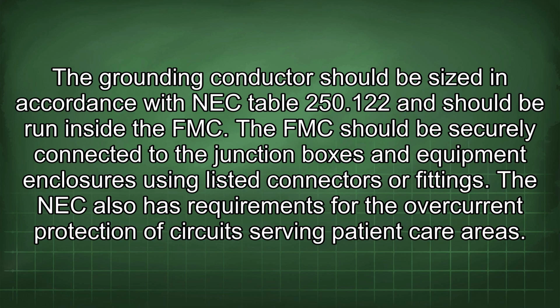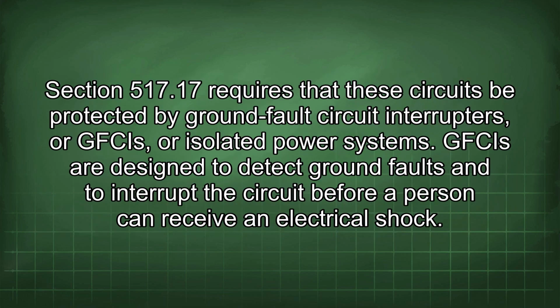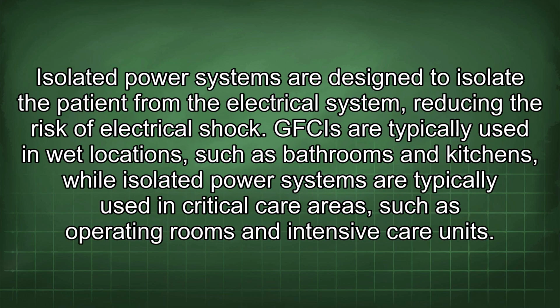The NEC also has requirements for the overcurrent protection of circuits serving patient care areas. Section 517.17 requires that these circuits be protected by ground fault circuit interrupters, or GFCIs, or isolated power systems. GFCIs are designed to detect ground faults and to interrupt the circuit before a person can receive an electrical shock. Isolated power systems are designed to isolate the patient from the electrical system, reducing the risk of electrical shock. GFCIs are typically used in wet locations, such as bathrooms and kitchens, while isolated power systems are typically used in critical care areas, such as operating rooms and intensive care units.